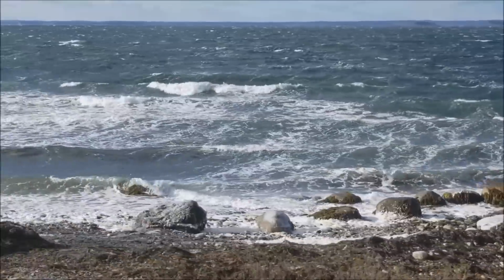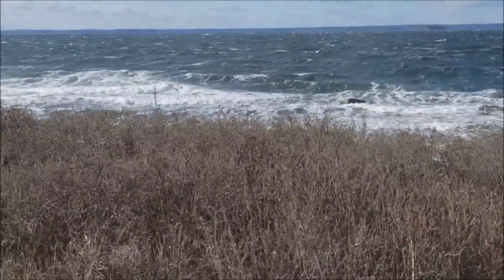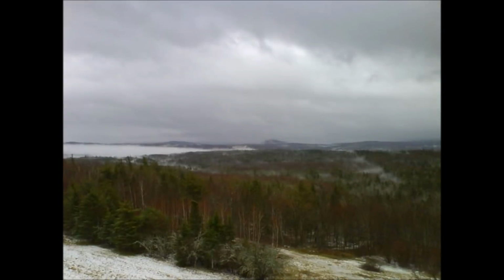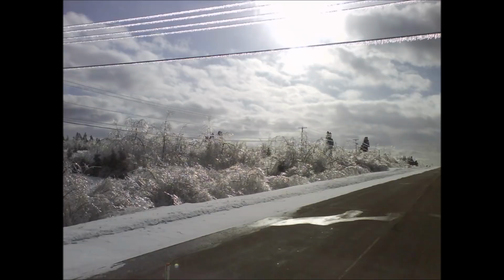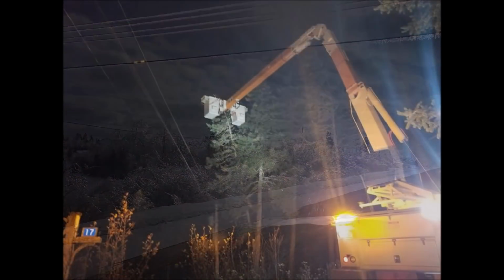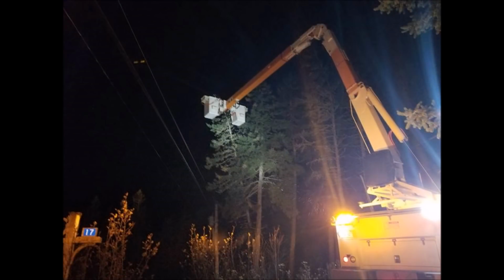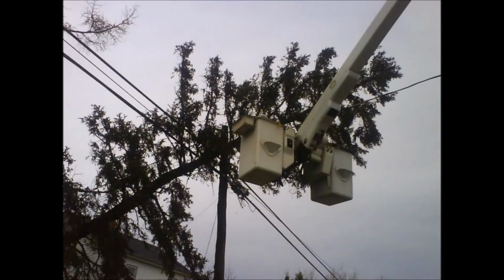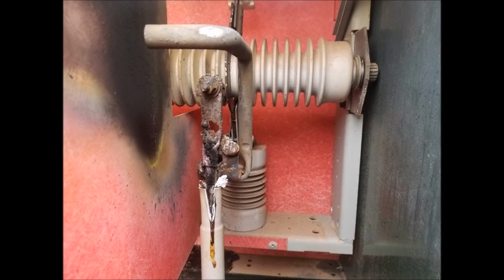Another guiding factor as we search for the cause of the outage is the type of weather. For example, if it's misting out or heavy fog, we may focus more on searching for cracked or broken insulators. During extreme cold, we may have to open some transformers to reduce load on the line before attempting to re-energize it. When it's really windy out, we may tend to pay less attention to all those things while simply looking for a tree that has fallen over on the line. It can sometimes be difficult to find the problem when the cause doesn't follow a typical trend.